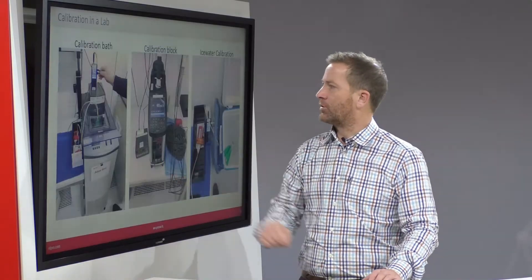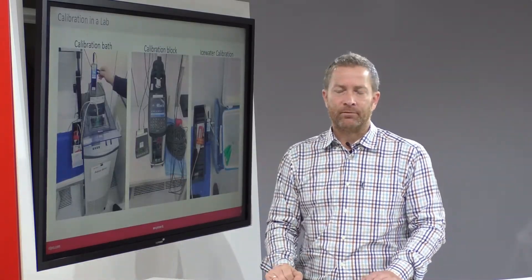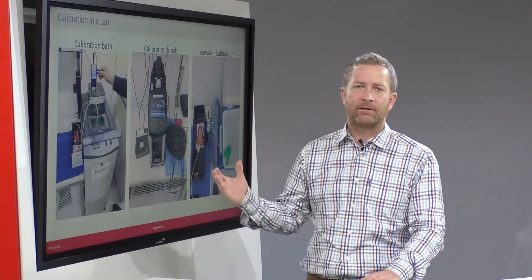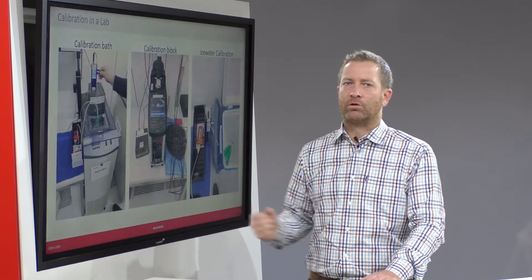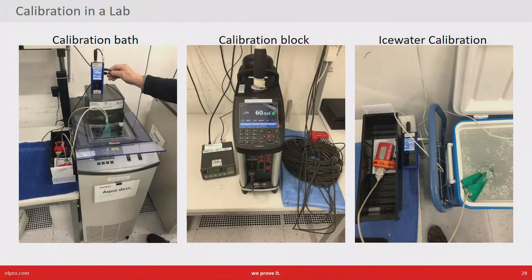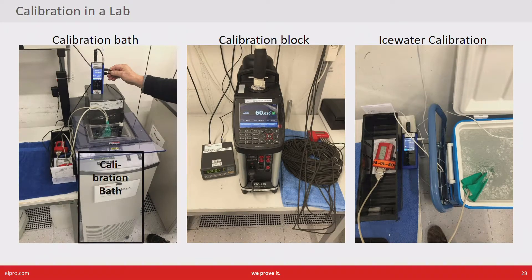I've taken a few pictures in our calibration lab showing three different techniques and devices used to perform calibration. On the left-hand side you see a calibration bath. As a liquid we use either distilled water or ethanol, and we can calibrate devices from minus 20 to plus 70 degrees. Calibration baths have the huge advantage of providing a lot of space, so you can dip entire devices inside the liquid.